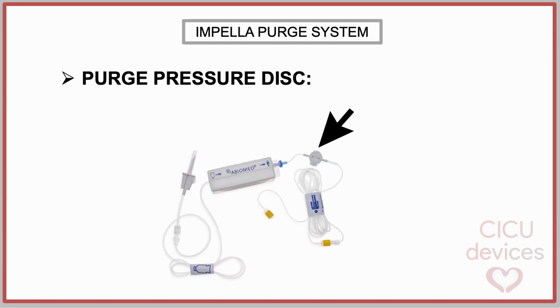Next, the purge pressure disc is a key internal component of the Impella Purge System, designed to monitor the pressure of the purge fluid delivered to the motor housing. By responding to changes in purge line pressure, it allows the console to continuously adjust purge flow in order to maintain a protective pressure barrier within the motor housing.